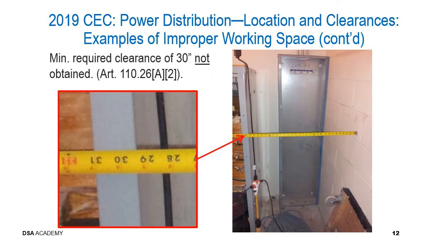These two images also show another example of an improper working space. The image on the right is basically showing a simple panel, an empty panel box with some conduits run to the top, and the project inspector is pulling his tape on this space that is in front of the panel. And as we recall, the minimum required working space width in front of any panel is 30 inches.